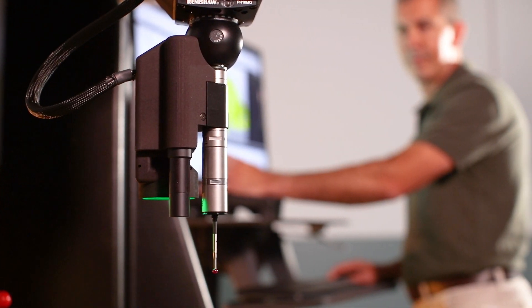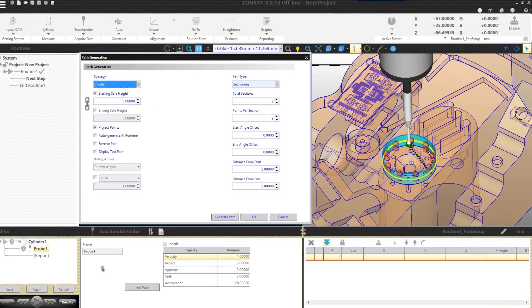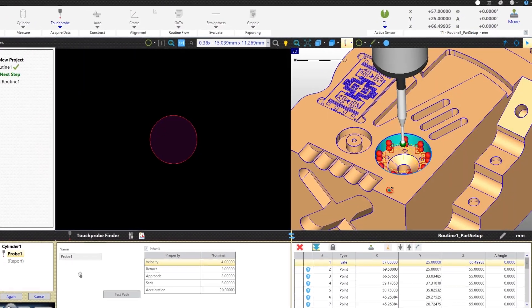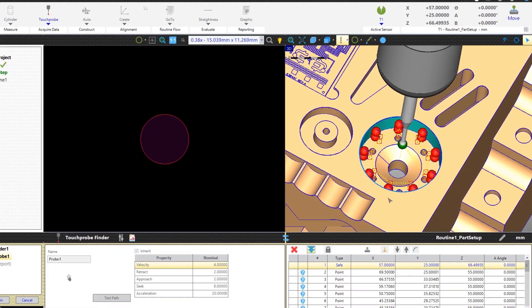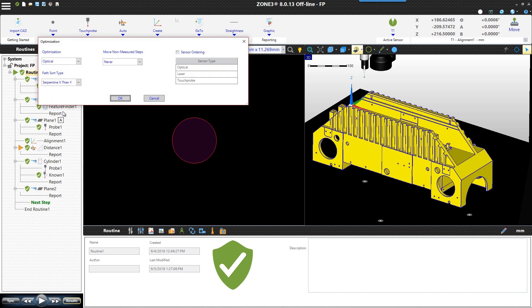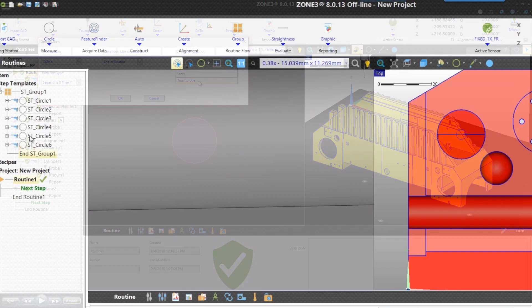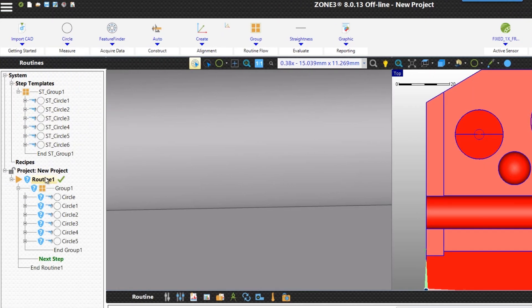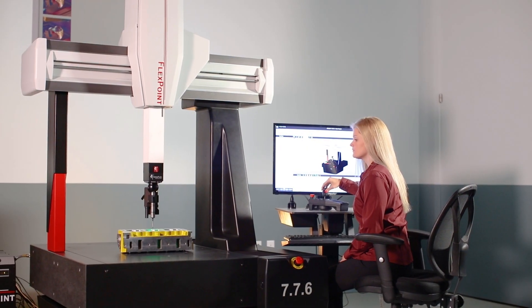Zone3 offers many sophisticated features to make programming easier and make programs run faster. Zone3 allows automatic definition of safe points, clearance zones, and probing paths for the sensor cluster that consider both parts and fixture tooling. The built-in optimizer automatically selects the fastest measurement path to maximize throughput. Creating recipes, routines, and projects that can easily be adapted to families of similar parts is both fast and intuitive.